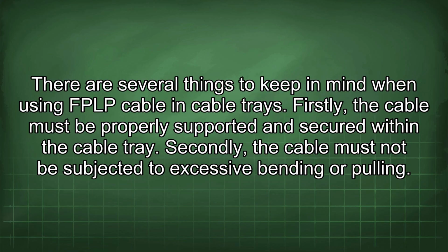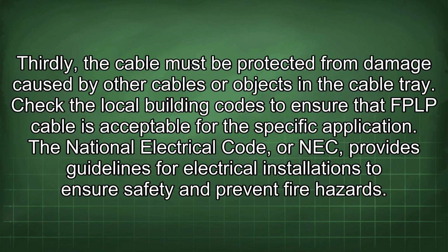Firstly, the cable must be properly supported and secured within the cable tray. Secondly, the cable must not be subjected to excessive bending or pulling. Thirdly, the cable must be protected from damage caused by other cables or objects in the cable tray. Check the local building codes to ensure that FPLP cable is acceptable for the specific application.